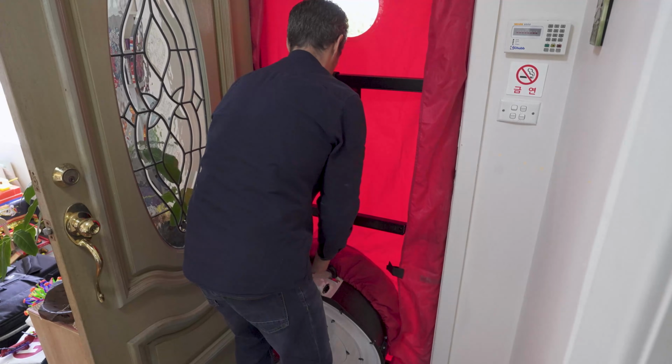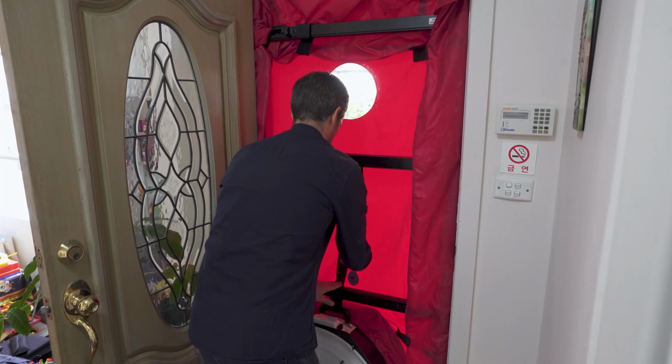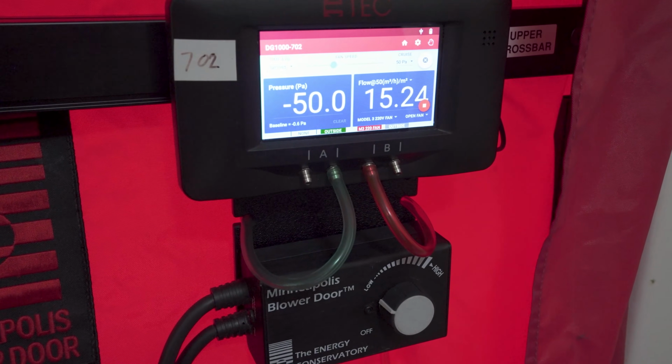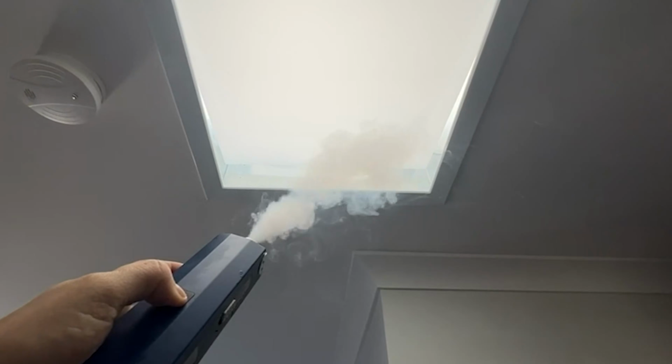Doing a blower door test on this house, in positive direction, I get about 4 air changes per hour more in the positive direction than the negative direction. Why is that? Because in the positive direction, it's like a hand pushing this thing up and into the well and increasing air leakage. More air goes out than comes in. It's still quite leaky in the negative direction as well. And I can show that with fog. But what I'm going to try to do is create a durable seal here so that this doesn't leak.